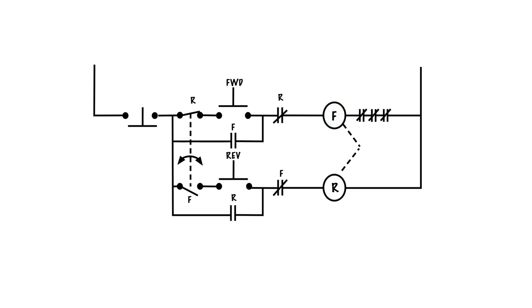I hit the stop button which de-energizes F which sends this back to normally open and this back to normally closed. So the motor might still be spinning through some inertia in the forward direction which keeps this zero speed switch open. So again until this motor has stopped spinning and this now closes, I can hit this reverse button as much as I want but the power can't get through.